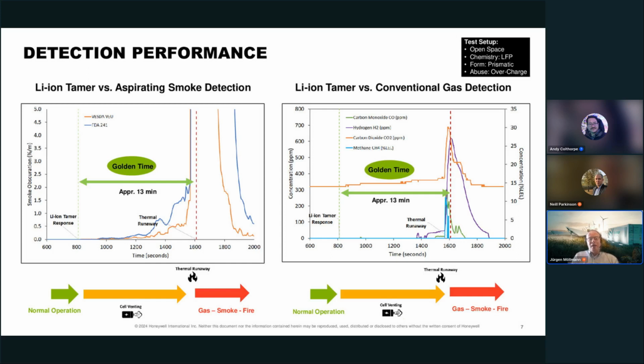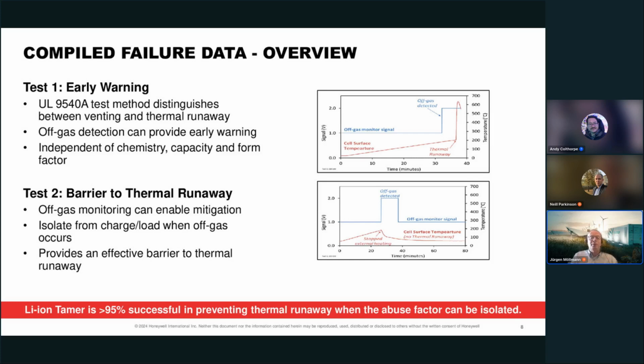We also did other tests, like over temperature. We used different cell chemistries and different form factors, and therefore we have a variation in this golden time, between 5 and 25 minutes. For our presentation here we use the 13 minutes as an average time to prevent the thermal runaway. Going the next step forward, the early warning is basically also using the UL 9540A test method. Here you see as well a temperature increase by external heating, and several minutes before the thermal runaway, the off-gas detection can detect the first electrolyte solvent vapor. So, a barrier to thermal runaway.